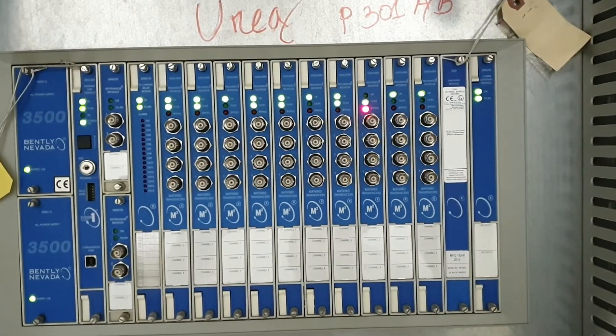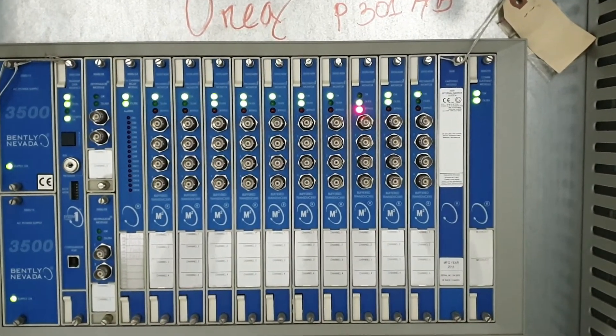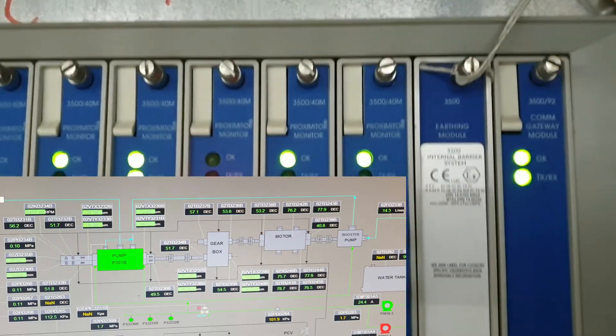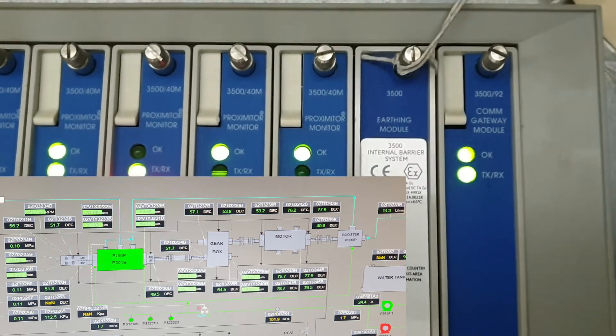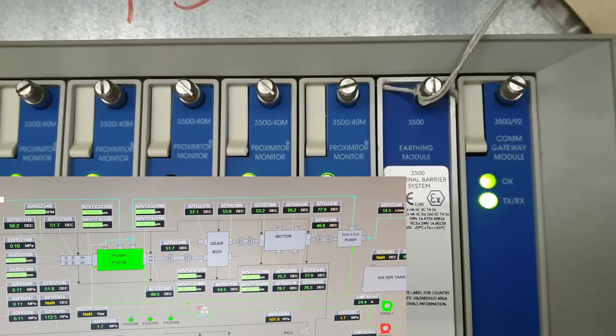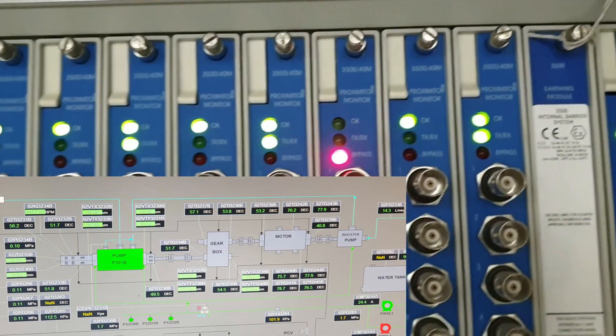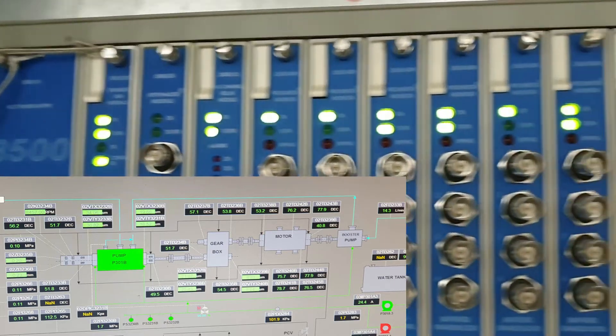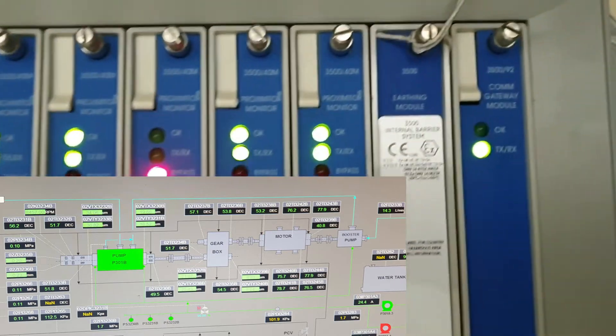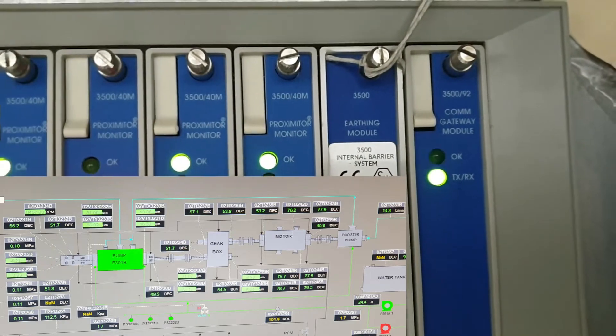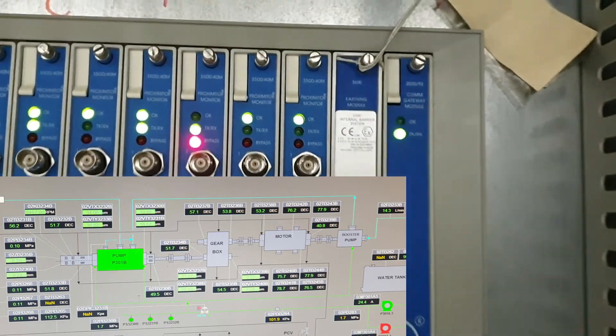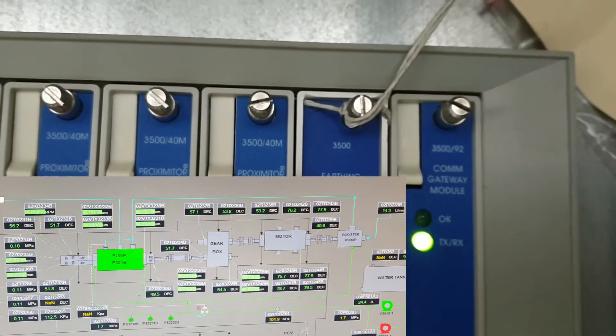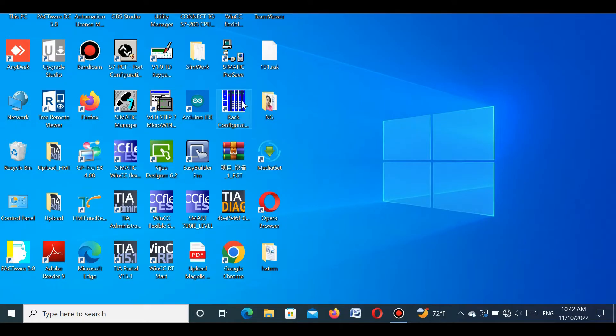Dear viewers, I will show you that the communication gateway module of the Bently Nevada 3500 system is not communicating with the third party system or DCS controlling system. The communication module LED is okay, but the transmitting and receiving LEDs of the communication gateway module are not blinking. For that reason, it cannot communicate with the DCS system and cannot transmit data. This is because the communication gateway module is faulty or damaged.